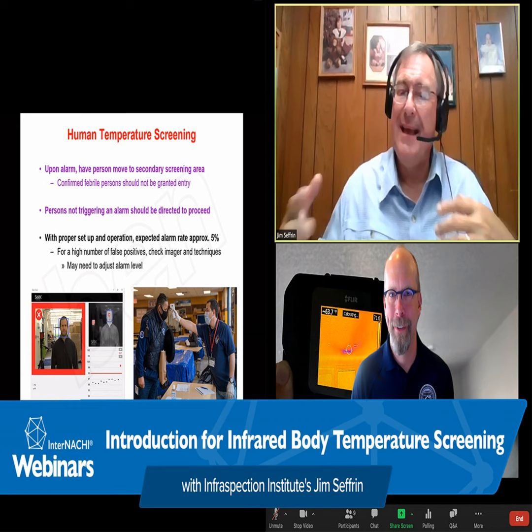Next thing you want to do, regardless of your imager type, is you're going to power up your imager. If your imager is supplied with one, you power up your black body reference source and the imager. Make certain that you allow sufficient time for the black body and the imager to stabilize. Depending upon your instrument, this could take as much as 30 minutes.